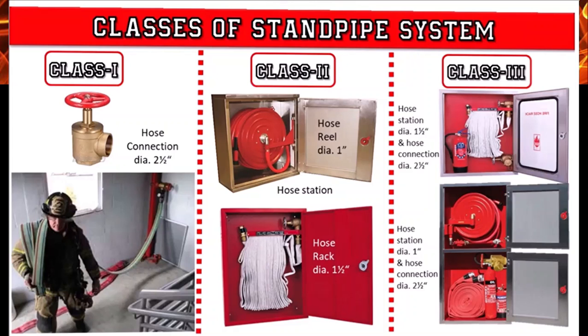So, in summary, Class 1 system features 2.5 inch hose connections that can only be accessed by firefighters during an emergency. Their outlets are usually located within the stairwells of buildings, and they are restricted to use by professional firefighters because the system's high pressure makes controlling the hose difficult. As a result, firefighters must bring a hose to the site that specifically attaches to the connections.